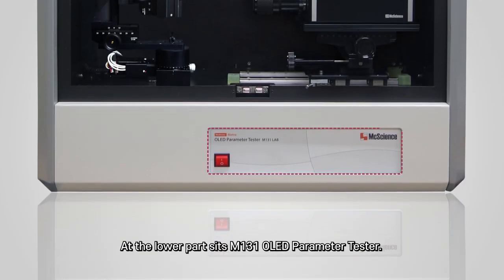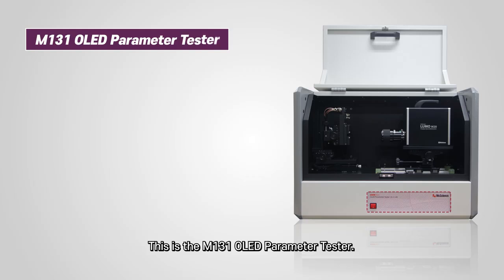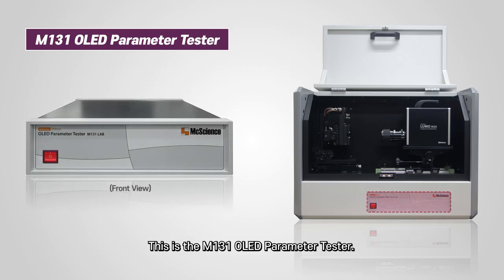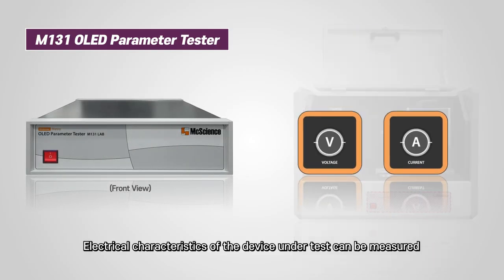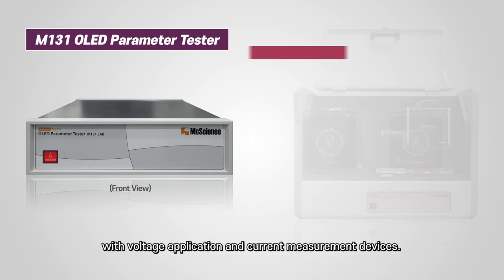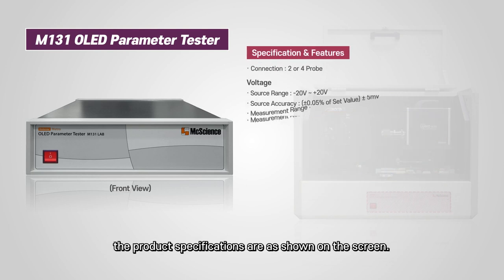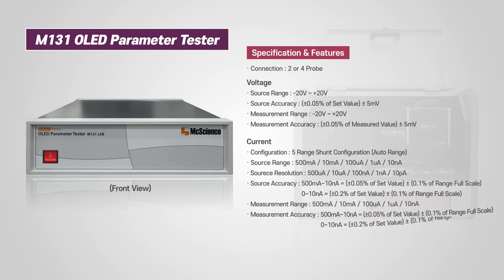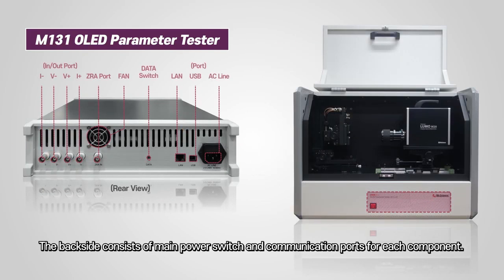At the lower part sits the M131 OLED parameter tester. This is the M131 OLED parameter tester. The electrical characteristics of the device under test can be measured with voltage application and current measurement devices. The product specifications are as shown on the screen. The backside consists of the main power switch and communication port for each component.